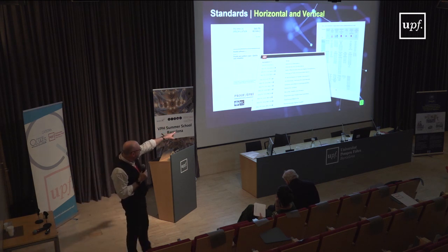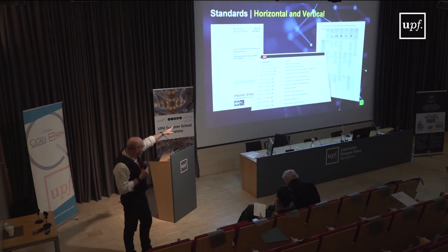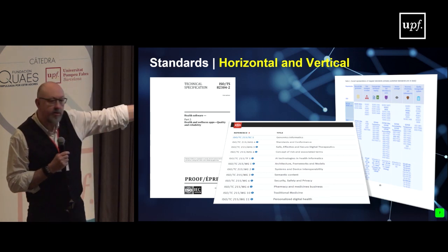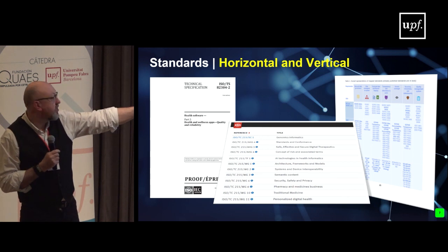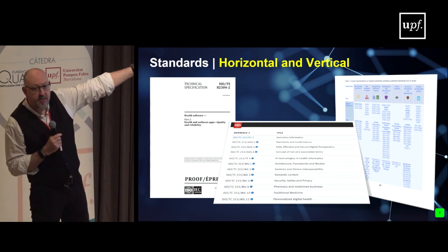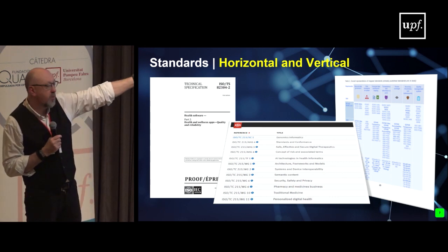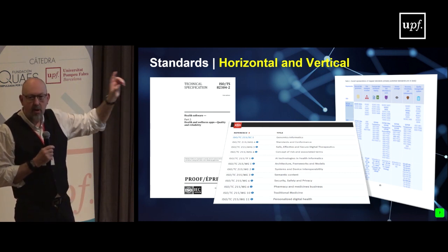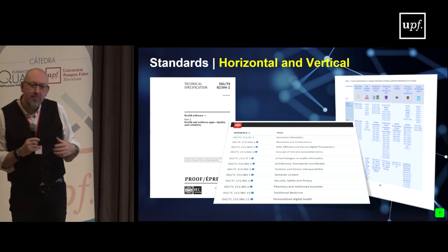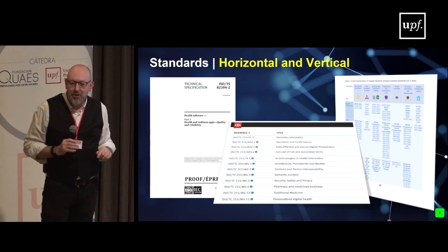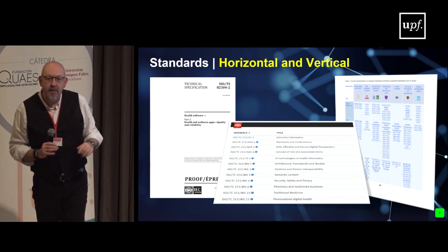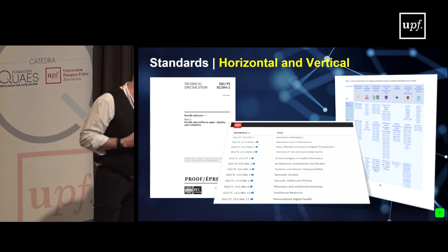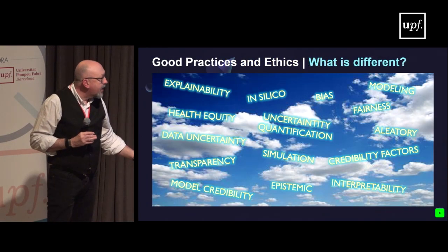You also have vertical general standards, like the ISO ones there for TC 215. Depending on your areas of interest, you can jump up and down that and see there are generic vertical standards for the healthcare industry. And then sometimes you'll get a very specific technical standard. That's where you'll find the notified bodies being very, very specific. If you're at the beginning of something, it's always worthwhile doing a little literature search just to see what's out there. That way you have guide rails, and something to get beyond, because ultimately you want to demonstrate that you're doing more than the standard.